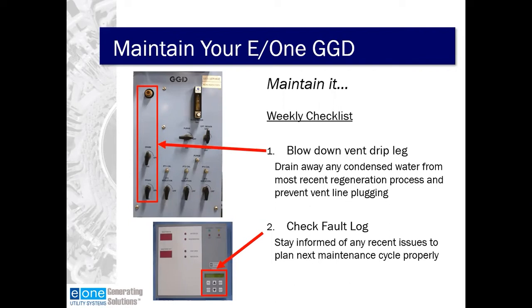The dryer is designed to operate in a hazardous area, so there is no inherent risk to the dryer. It's important to just follow safe plant procedures when it comes to the possibility of venting hydrogen gas during this process. We talked about checking the fault log in the previous slides. Again, on a weekly basis, scroll through that to make sure any intermittent events that may have occurred are captured. You can stay informed of that and make appropriate plans for the next maintenance cycle when those opportunities arise.